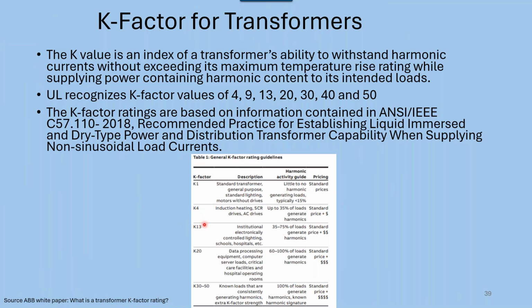So K1, little or no harmonics. K4, a lot of times when I specify a transformer, I'll tell them I want a K4 by default. The reason for that is the difference in cost between a K1 and a K4 is almost none, and that'll get me up to 35% harmonics, which is good. K13 is 35 to 75. So K9 is probably 50%, somewhere in between these 2 numbers. K13, I don't see that often. K20, I rarely see, and K30, I don't think I've ever seen.